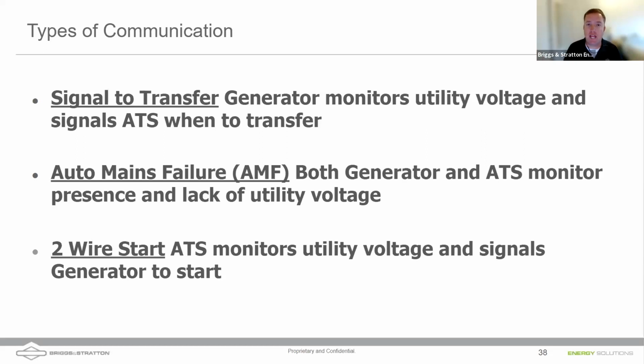And once generator and utility generator voltage has come up and the utility is down, it will go ahead and transfer. The additional way to do this is with our generators, you can have the generator monitoring voltage, right? And what you have to do is disable that, and then use a 2-wire signal to start. Really what you're now doing is taking the control out of the generator and putting the control into the inverter. And honestly, it could be other people's inverters that can start our generators. It doesn't have to be ours.